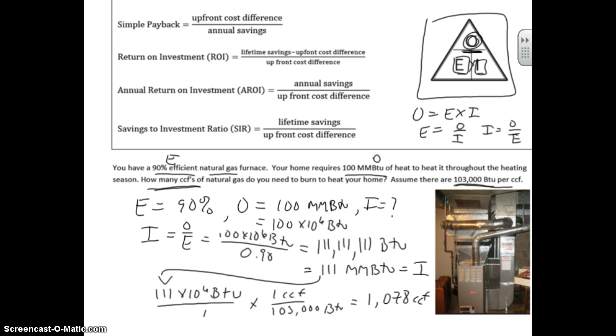If we know we need that much heat and we know how efficient our furnace is, we can tell the input. And then ultimately we can tell that we need a little over 1,000 CCFs. Now we could easily convert that to cost. Let's say it's $1.50 a CCF. We could multiply that to 1.5. But that is how you can use your efficiency equation to calculate the necessary input given an output and an efficiency.